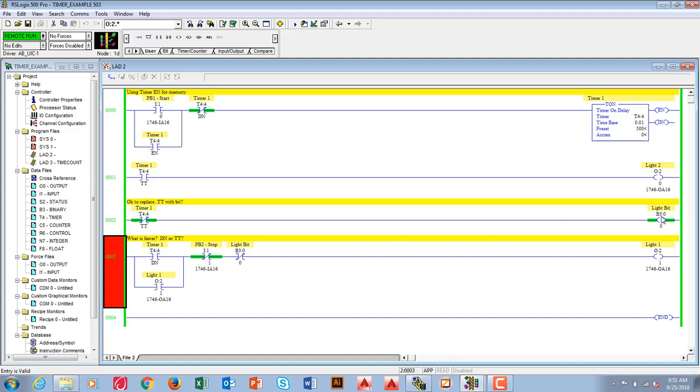And if this rung's true, this bit gets a 1 written into it because it's logically true here. And then that light bit causes this, which would normally have a 0 in it, meaning it was true, to get a 1 in it. And the 1 makes this false. So you got to be careful when you address like a double not here, a double negative, because it will cause your output to change state. Hopefully that makes sense to you.